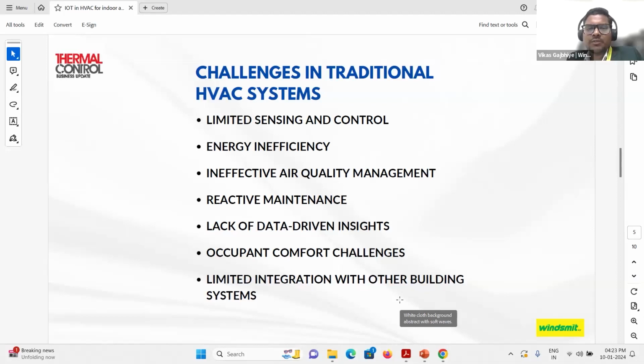Second last, the occupant comfort challenges. As the system is just trained to maintain 24 degrees Celsius irrespective of any condition, we will see or experience hot spots and cold spots in the building or at the corner of the building, which is not desirable. And last, the limited integration with other building systems. There is a limitation in integrating other utilities like lighting controls, fire and security, and access control, because the entire data has to be stored in one place, dedicated to a particular memory space. In the conventional and traditional HVAC system, there is limited storage space. Hence, the synergy of the building is hampered, and again the data maintenance effort is very huge.